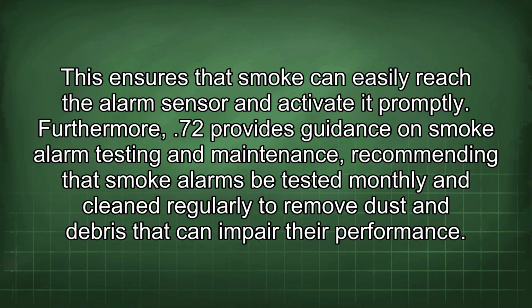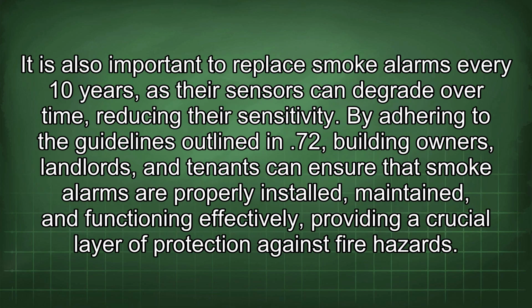Furthermore, NFPA 72 provides guidance on smoke alarm testing and maintenance, recommending that smoke alarms be tested monthly and cleaned regularly to remove dust and debris that can impair their performance. It is also important to replace smoke alarms every 10 years, as their sensors can degrade over time, reducing their sensitivity. By adhering to the guidelines outlined in NFPA 72, building owners, landlords, and tenants can ensure that smoke alarms are properly installed, maintained, and functioning effectively, providing a crucial layer of protection against fire hazards.